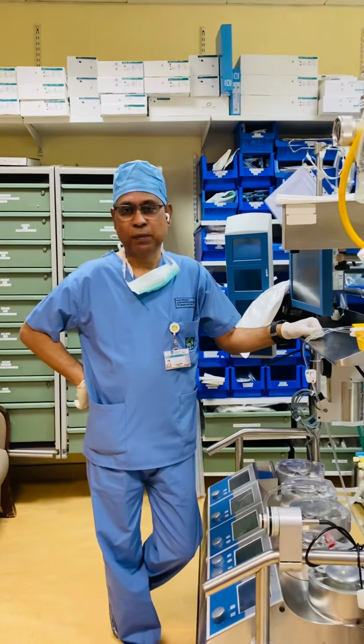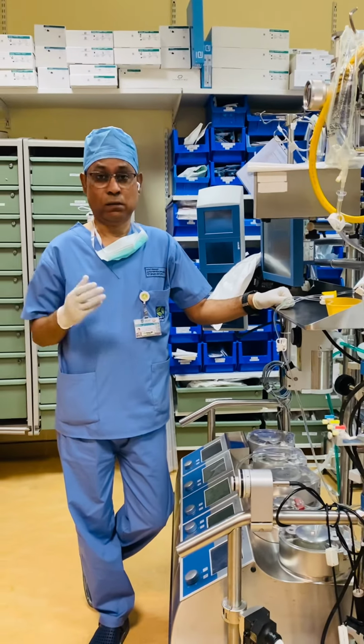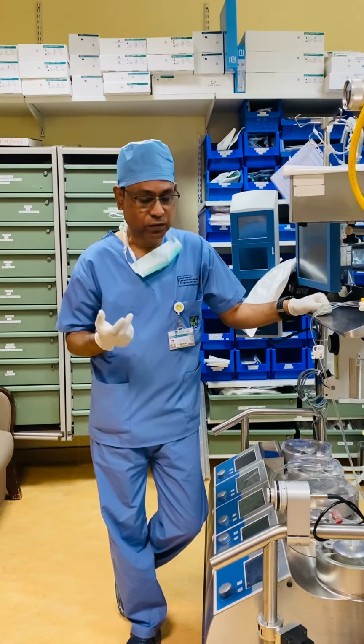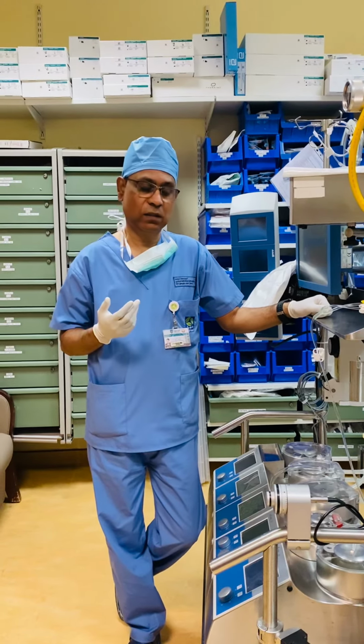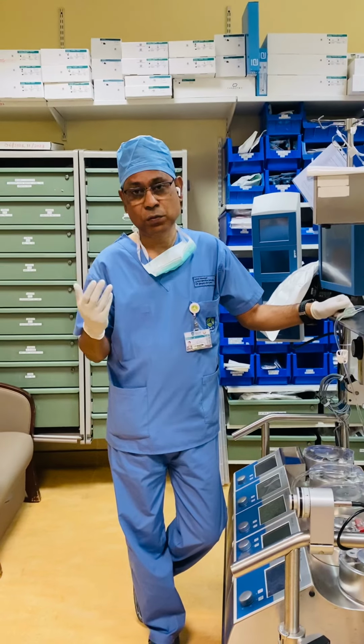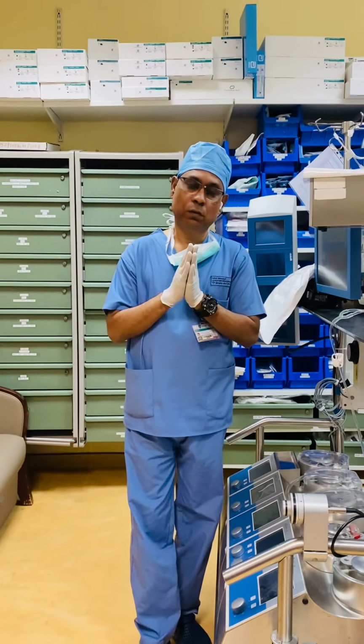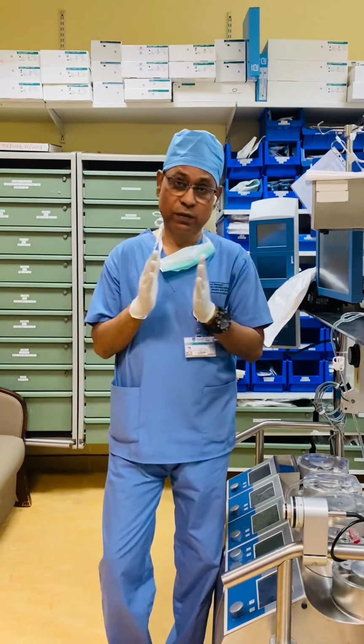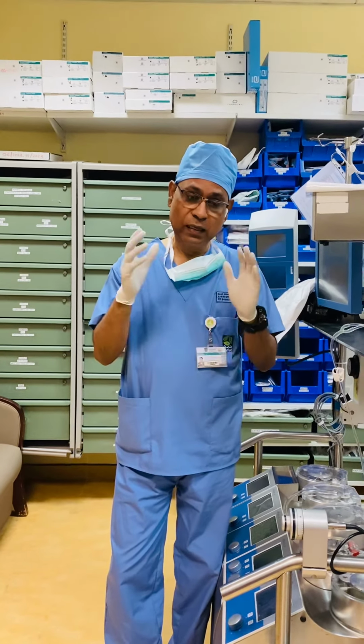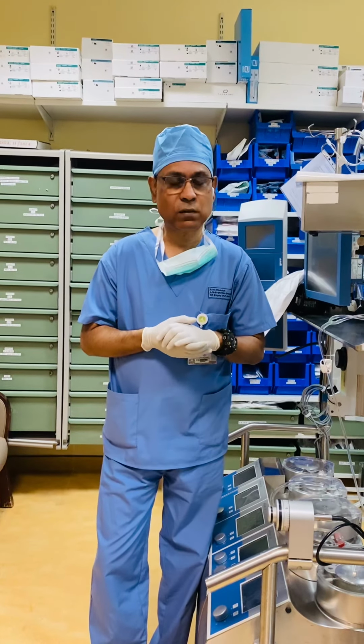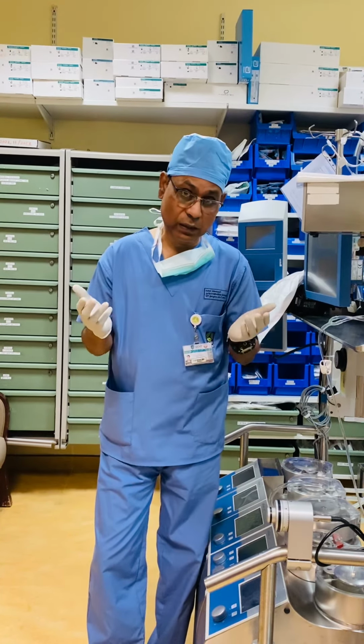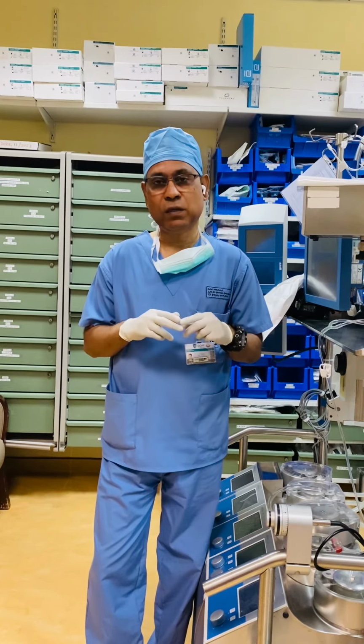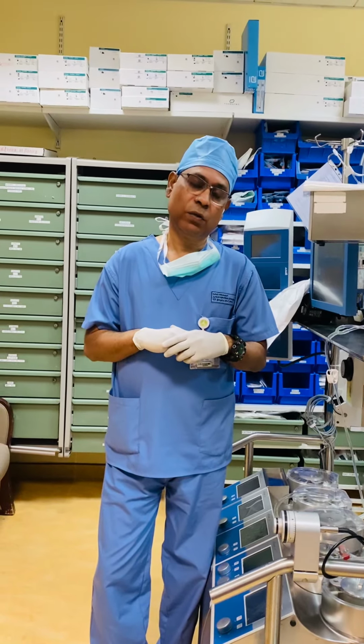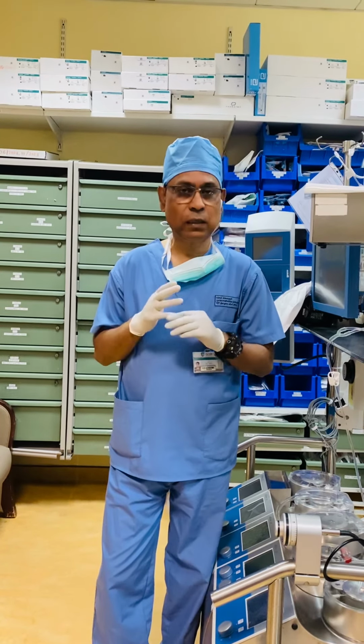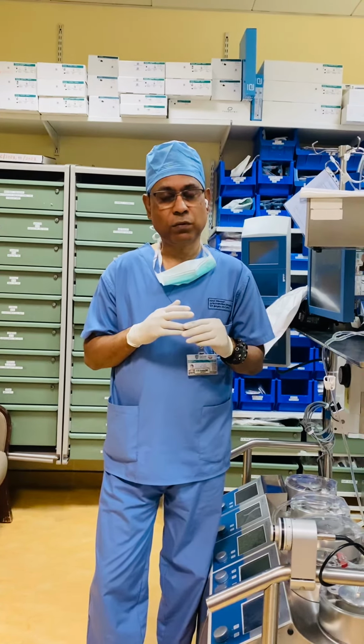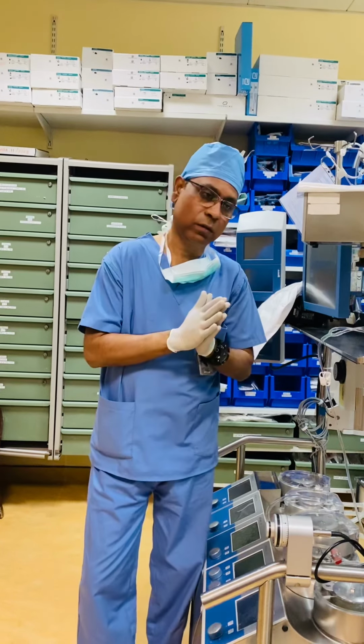So in a cardiopulmonary bypass, we require the oxygenators, cardiotomy reservoir, heat exchangers, and of course the tubings. To describe the tubing, today we are going to highlight some points about the tubings. Which types of tubings are we using in a cardiopulmonary bypass? Normally we are using two types of tubings: silicone tube and polyvinyl chloride tubes. I mean PVC tube and silicone tube.